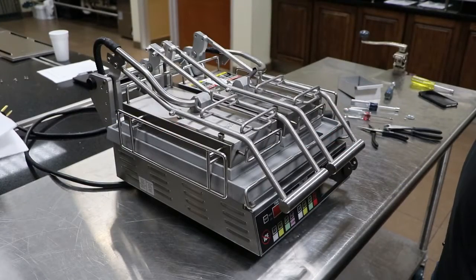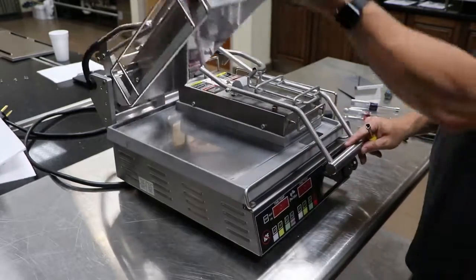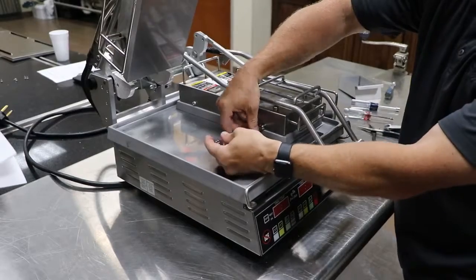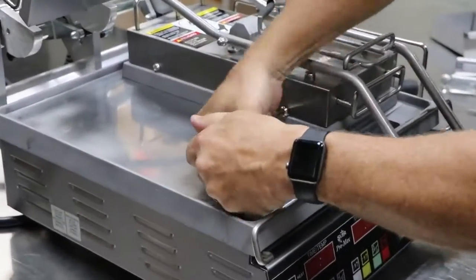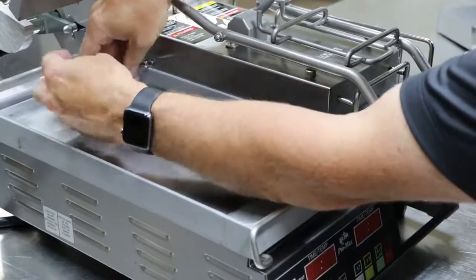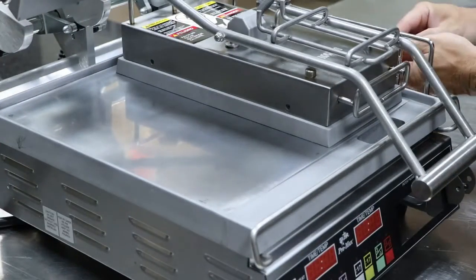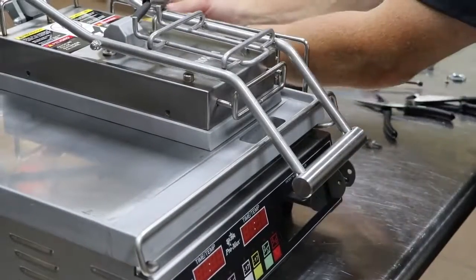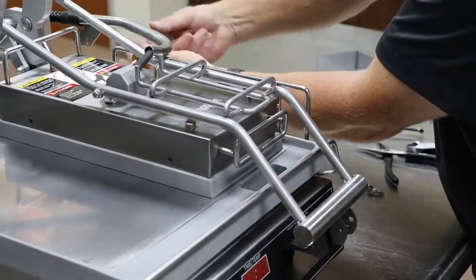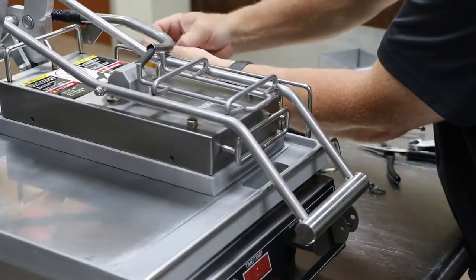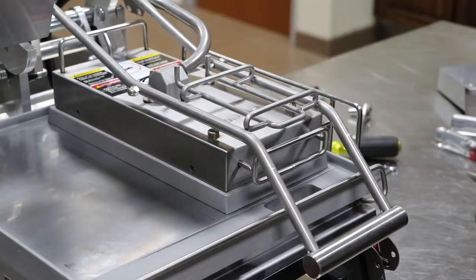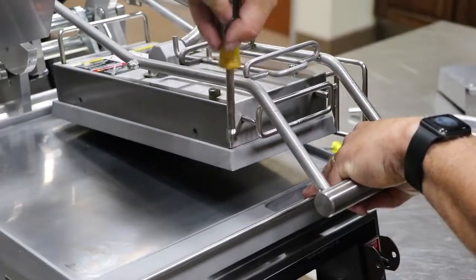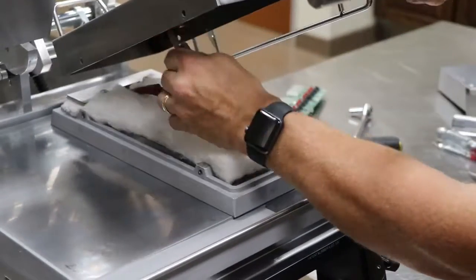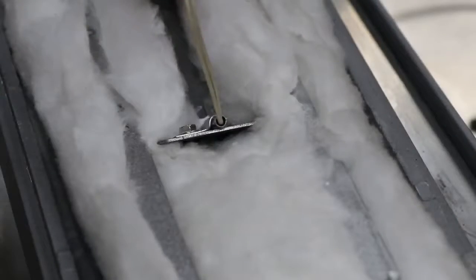Next, remove the 4 5/16 inch screws from the top platen. Remove the top platen from housing while holding on to the front handle. Pull the element and probe wires toward the top casting, opening top housing to relieve wire strain. Loosen probe clamp with 1/4 inch nut driver and remove probe from top casting.